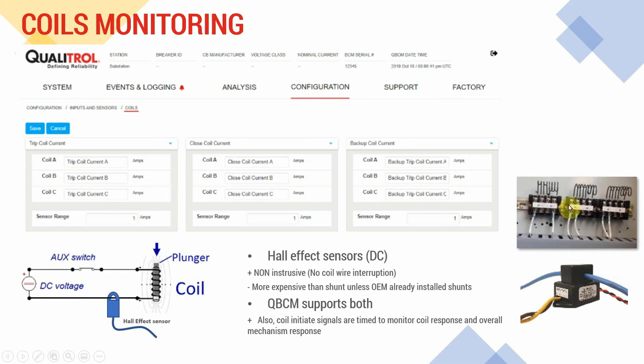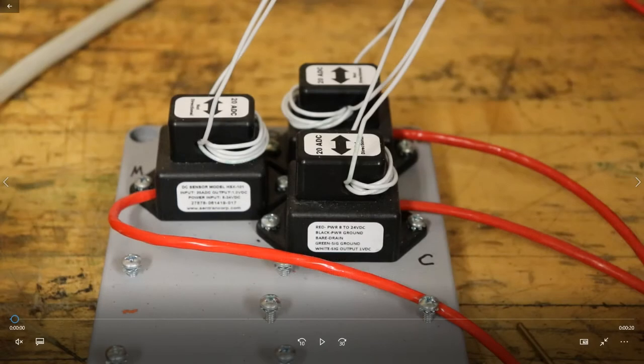Alternatively, shunts can be installed in series with the coil supply cable and the breaker monitor can measure current using the shunts. The choice of Hall effect sensors versus shunts primarily depends on whether it's a new breaker manufacturing or if it is a retrofit case. In case of a retrofit, installing or adding shunts in series with the coil supply cable can be very invasive and may void the circuit breaker warranty. Hence, a Hall effect sensor, which is a non-intrusive method of measuring the coil currents, is the most recommended method for retrofit cases. Let's take a look at how Hall effect sensors are wired.